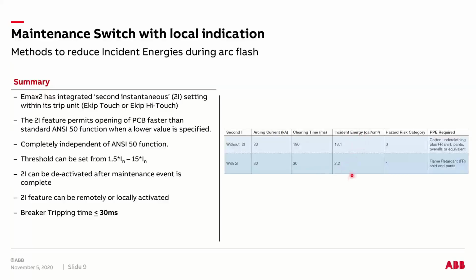So the incident energy level is significantly reduced to less than about 2.2 calories per centimeter square, which is categorized as HRC category 1. The second instantaneous is an inherent feature of our low voltage breakers, as I mentioned. It's a very popular device or option to use.